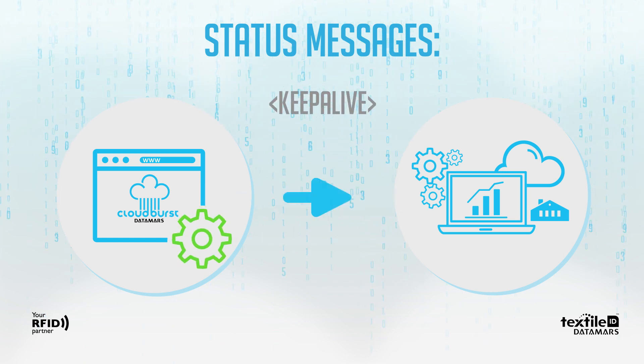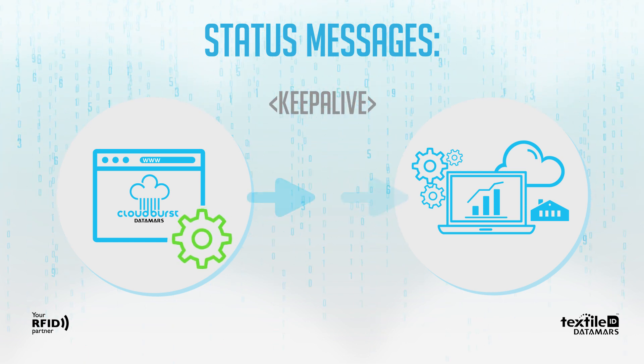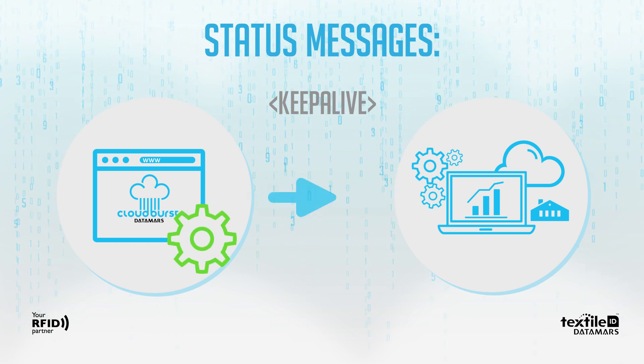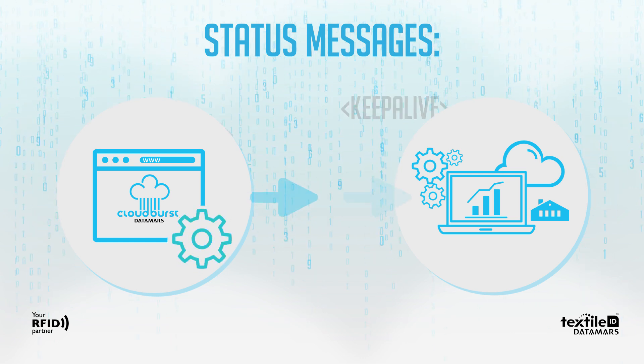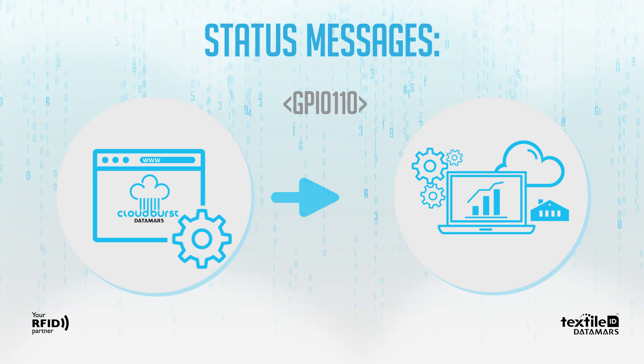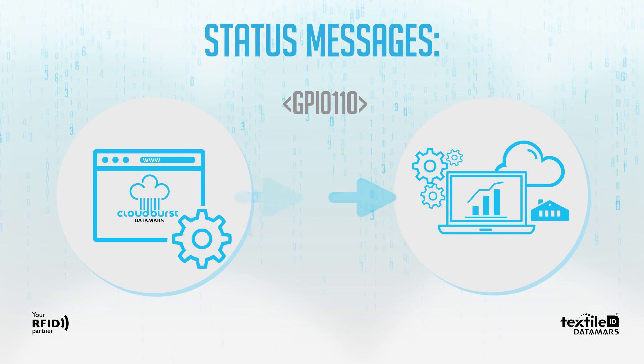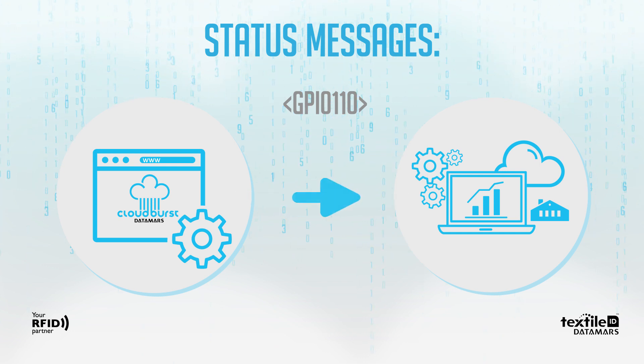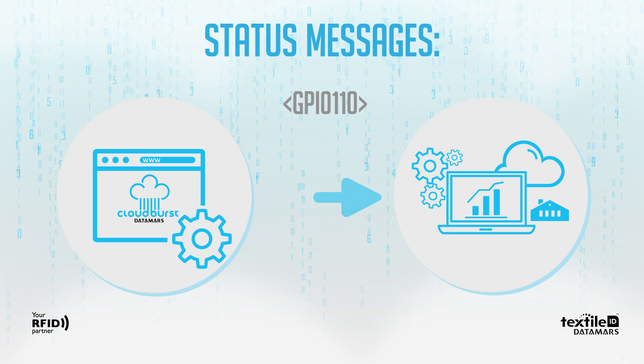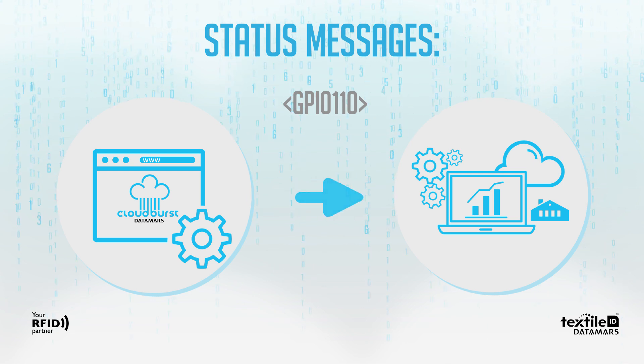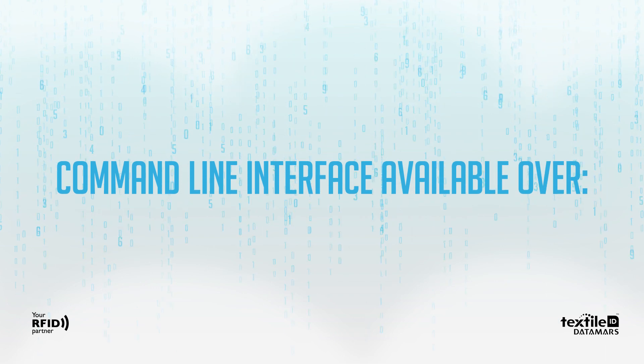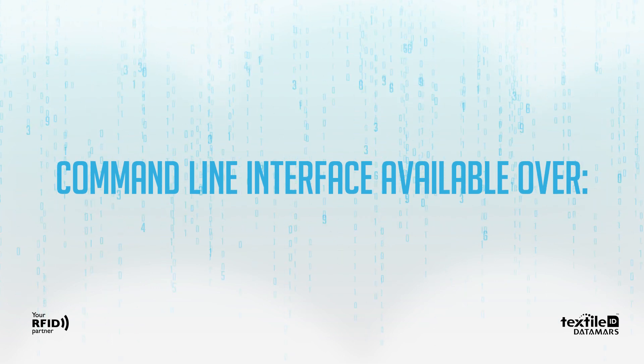'Keep-alive' is periodically sent to allow the upper software layers to check if the RFID system and physical link are alive. 'GPI' is sent every time the status of a GPI changes; the last four digits of the message represent the logic level of the respective GPI, which can be zero or one.